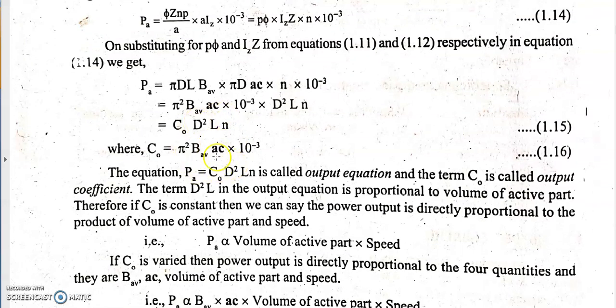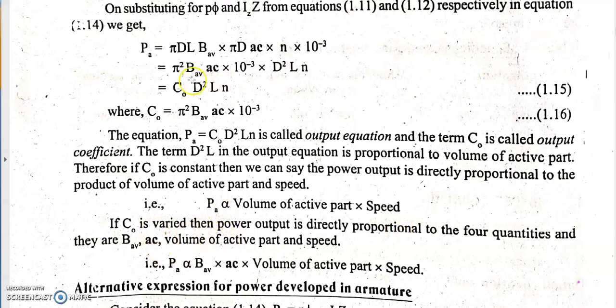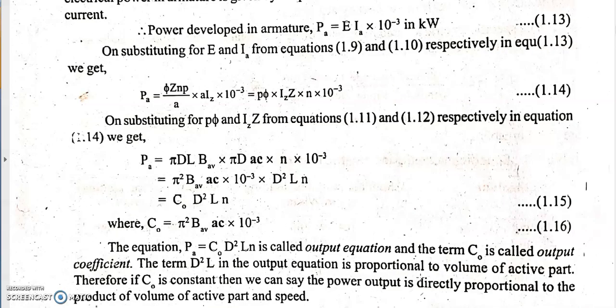The main dimensions of the armature — diameter D and axial length L — are found from this output equation. The product D²L represents the volume of the active part of the machine, which is the armature where energy conversion takes place. If C₀ is treated as constant, PA is proportional to D²L × n. If C₀ is variable, then PA is proportional to B_average × AC × D²L × n, which is the output equation from a design perspective.